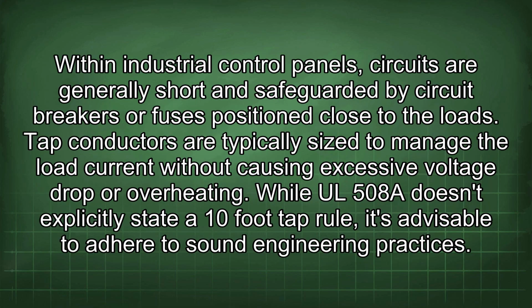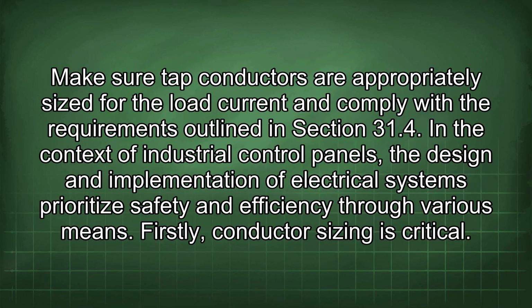Within industrial control panels, circuits are generally short and safeguarded by circuit breakers or fuses positioned close to the loads. Tap conductors are typically sized to manage the load current without causing excessive voltage drop or overheating. While UL 508A doesn't explicitly state a 10-foot tap rule, it's advisable to adhere to sound engineering practices. Make sure tap conductors are appropriately sized for the load current and comply with the requirements outlined in section 31.4.